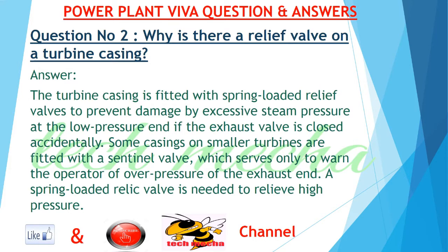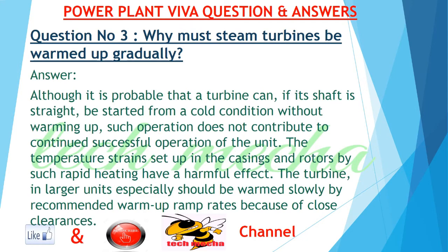Question number 2: Why is there a relief valve on a turbine casing? Answer: The turbine casing is fitted with spring-loaded relief valves to prevent damage by excessive steam pressure at the low pressure end, if the exhaust valve is closed accidentally. Some casings on smaller turbines are fitted with a sentinel valve, which serves only to warn the operator of overpressure at the exhaust end. A spring-loaded relief valve is needed to relieve high pressure.